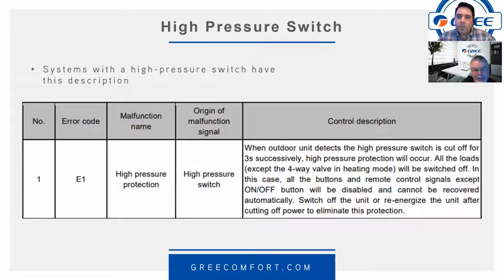Right. So what's your opinion, Daniel, on the likelihood of that occurrence happening? If you just go out there and pull the power, do a hard reset, wait 10 minutes and it clears the code, chances are you're not dealing with a failed pressure switch, correct? But you're going to eventually get another E1 error code, whether it be after you get home and sit down in your recliner to do your service reports, the customer calls you back. So it's important to not just reset but to inspect and test everything.